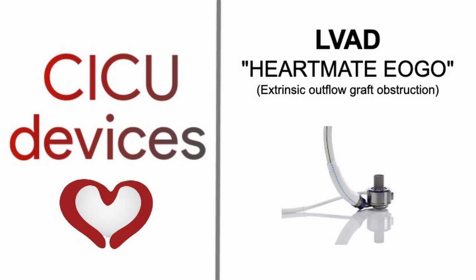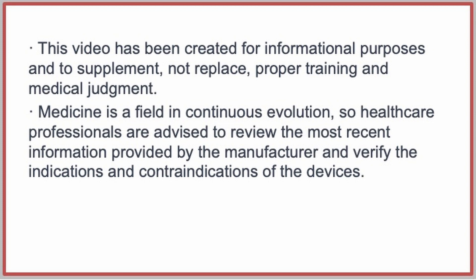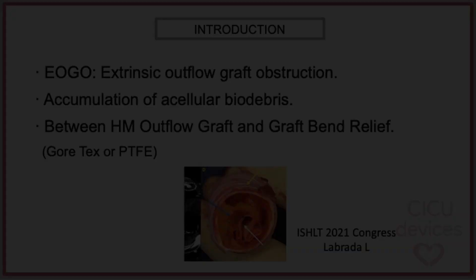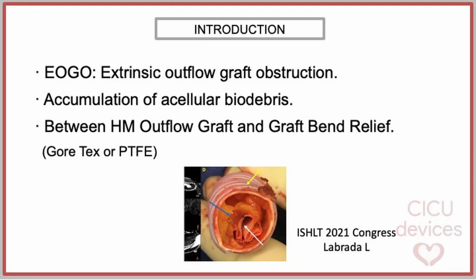Extrinsic outflow graft obstruction is triggered by the accumulation of acellular biodebris located between the Heartmate outflow graft and the outflow graft bend relief, or another component such as Gore-Tex or polytetrafluoroethylene conduit, or a wrap added by the surgeon during implantation.